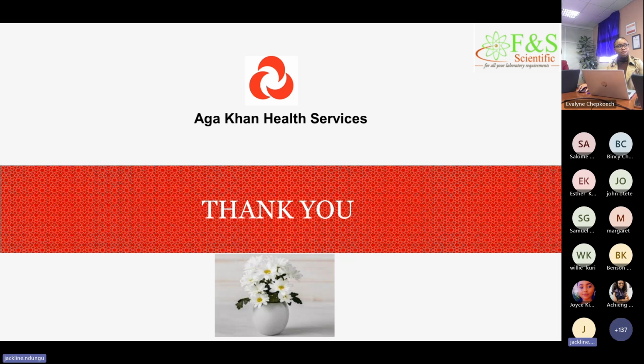And the many equipments, again, let's say, for example, you are at Aga Khan Hospital. The many equipments, and believe me, when you're dealing with clinical team, there are nurses, there are doctors, there are assistants who are working on that equipment. You cannot survive with manual processes. So what we have done is that we have automated the system. So when you are doing IQC, you have to have a lockout system. If the IQC has not passed, then they cannot proceed with patient testing. Otherwise, you'll be very depressed trying to run glucometer 1, glucometer 2, and there are over 60 glucometers around. There are over like 10 blood gas equipments.